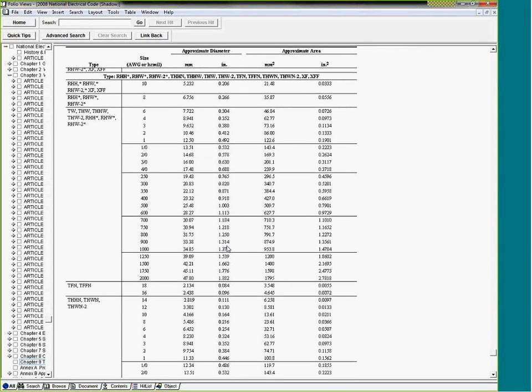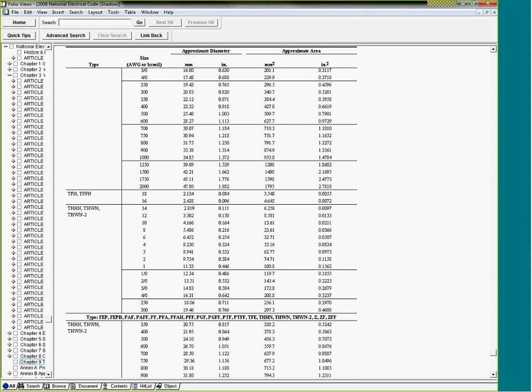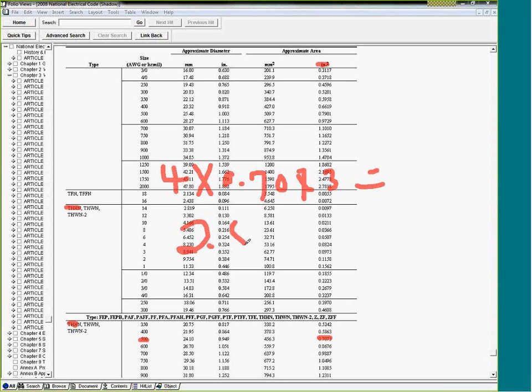Table 9, guys. If I have the cross-sectional area of a conductor, very interesting, of my conductor, I'm going to just highlight, I like THHN, and the conductor is 500 kcmil THHN, and the cross-sectional area of this conductor, 500 kcmil, is 0.7073. So I have 4 of them. You multiply this one by 4. That's easy to do, right? Your calculator handy. So 0.7073 times 4 equals 2.829. So that's basically how much I get, 2.82.